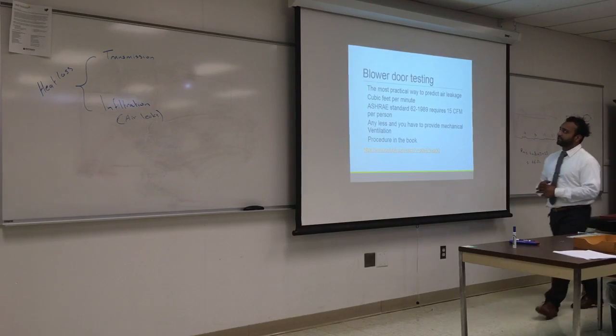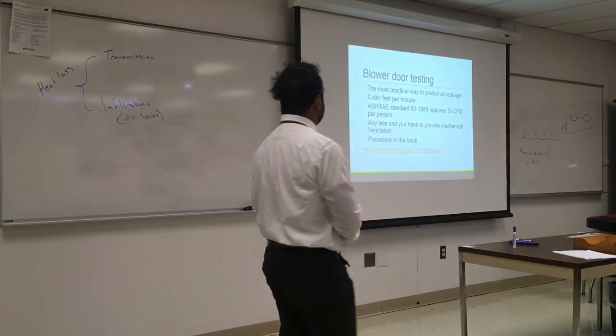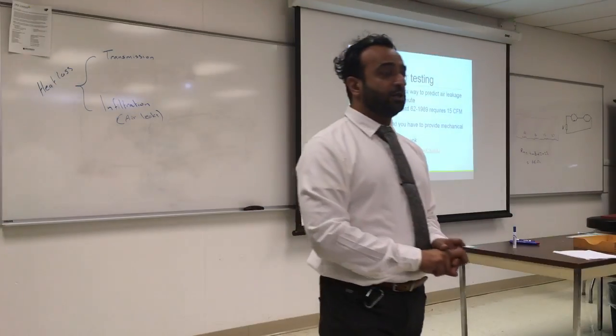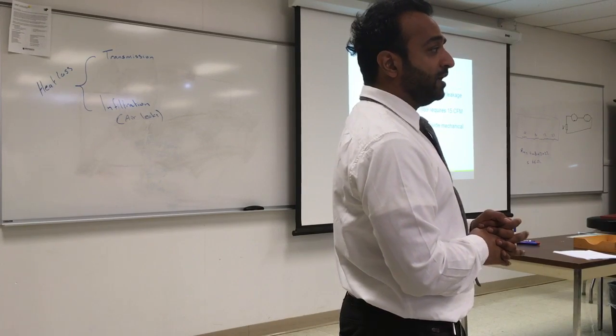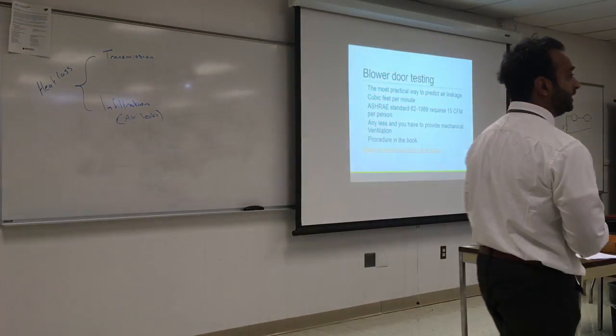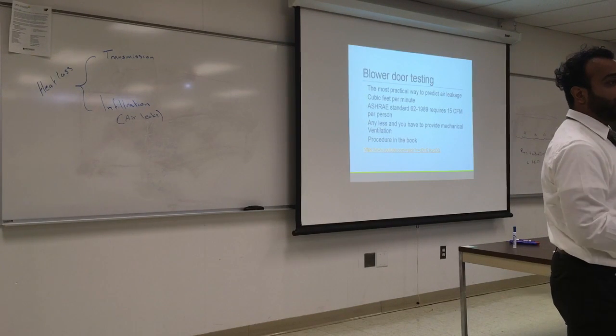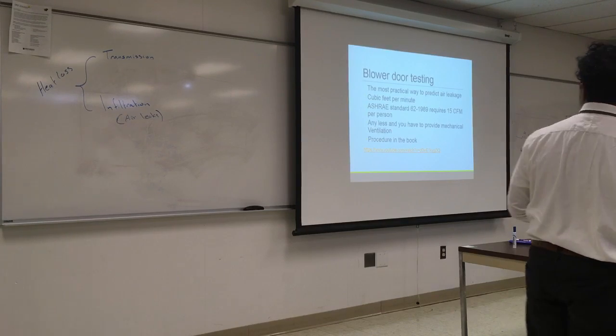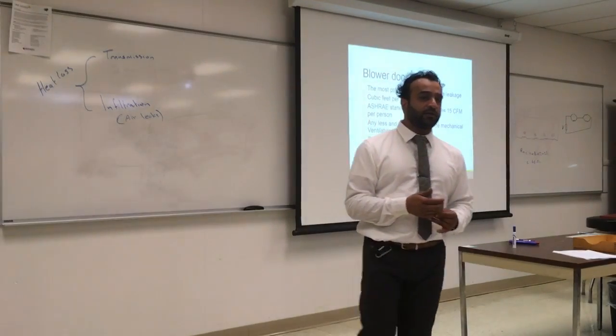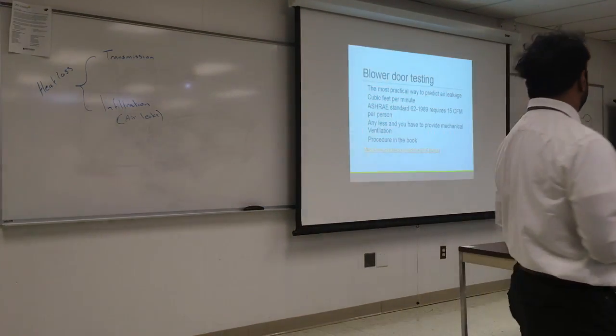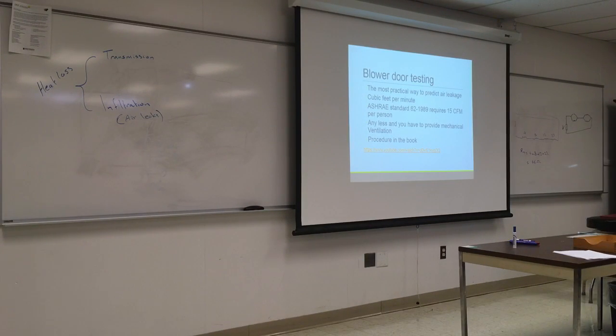Blower door testing is the most common one. If you work for Eversource or Columbia Gas or any power company they will send you somebody to do a blower door testing. It's for free. Because at least 50% of the heat loss in the house is done because of air exchange. It's the most practical way to predict the air leakage. And they give you the air leakage as cubic feet per minute CFM.